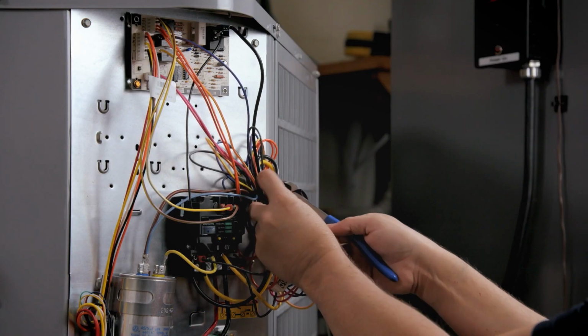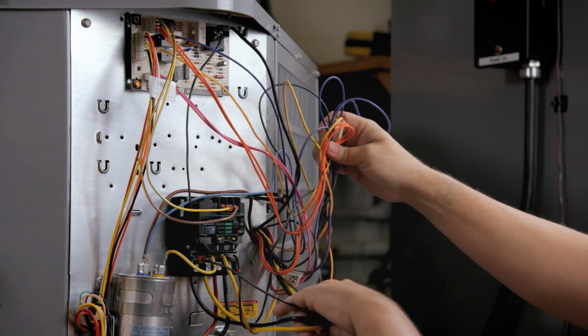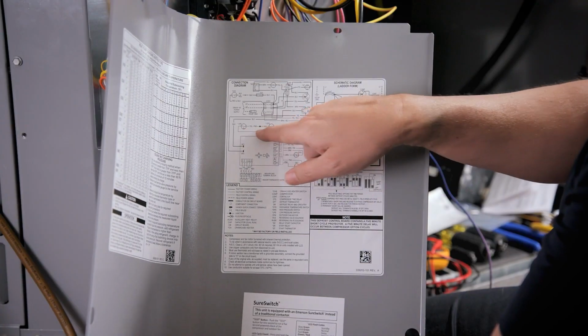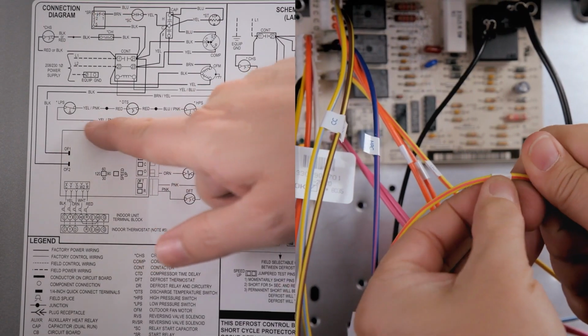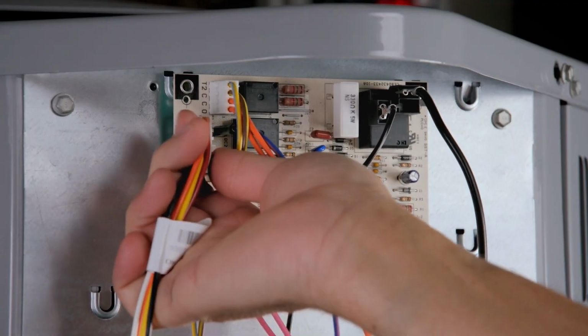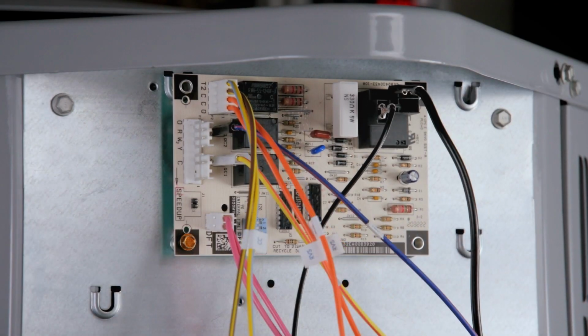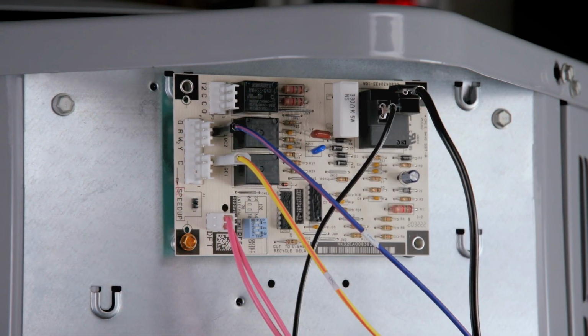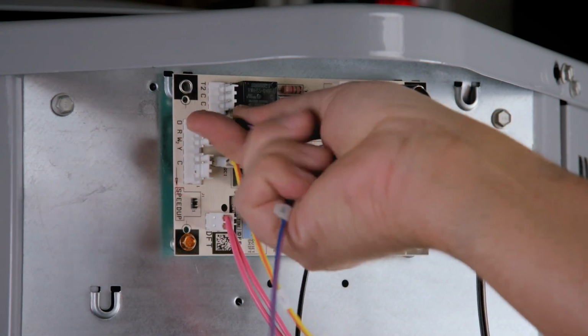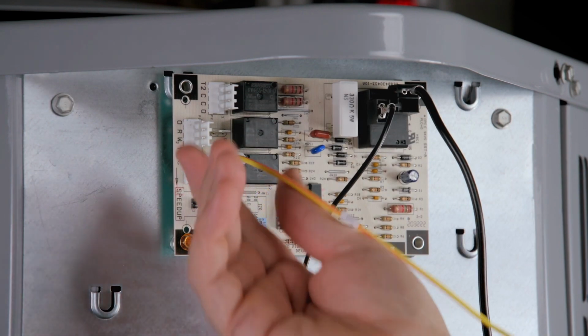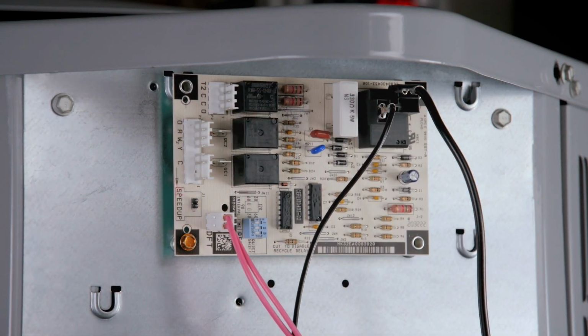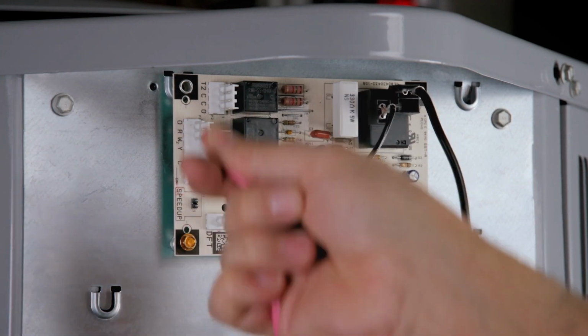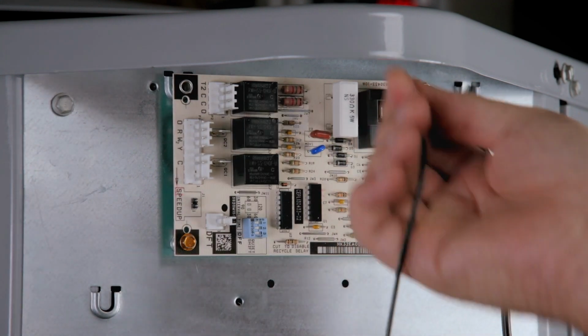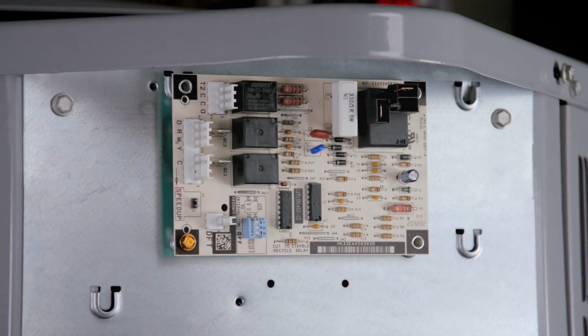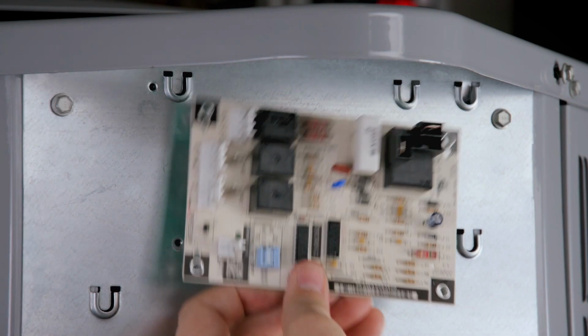Cut any straps securing wires. Using the wire diagram, apply supplied terminal wire labels. Disconnect the thermostat wiring. For this application, disconnect the contactor wires and reversing valve wires. Disconnect the high pressure switch wire. Disconnect the low pressure switch wire. Disconnect the defrost coil temperature sensor. Disconnect the condenser fan motor wires. And finally, remove the board.